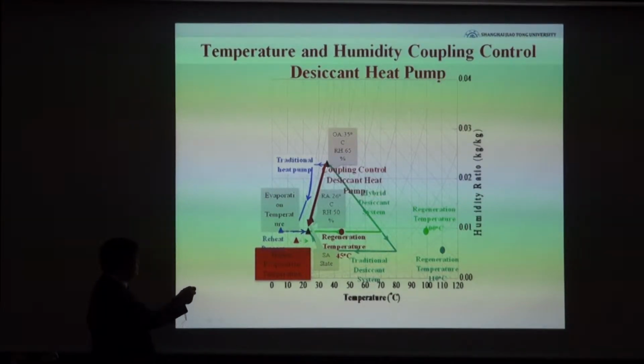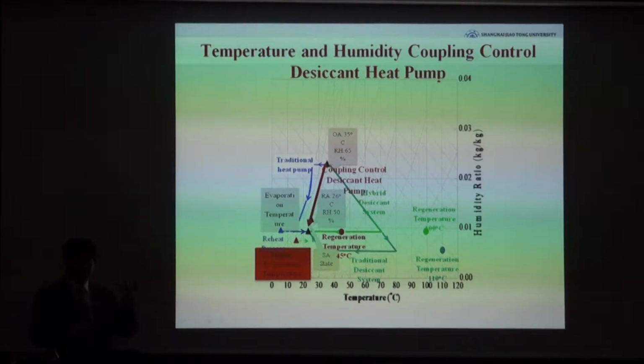And then some people consider using it with a heat pump. We have a desiccant rotor. It dehumidifies, but the air is not very dry, just a little bit dry. So the temperature is not very high, and then it is cooled down by evaporation, and you get a reasonable temperature. So in this case, it is a kind of desiccant rotor combined with a normal vapor compression system. It's called independent temperature and humidity control. Humidity is handled by a desiccant rotor, for example, and temperature is handled by the vapor compression system.